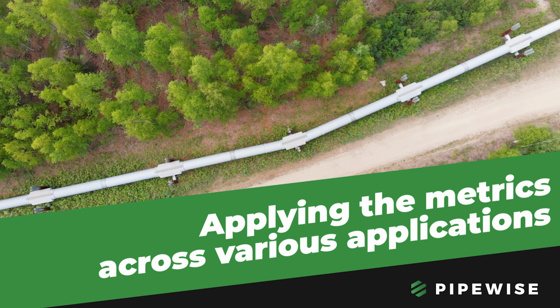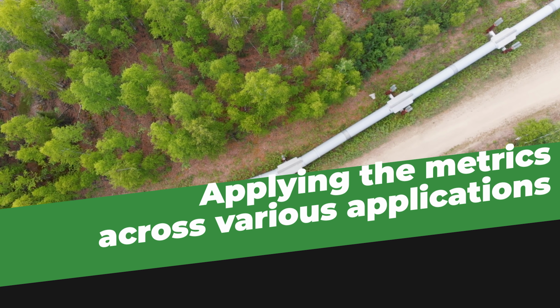Similarly, if we're predicting where along the pipeline that the leak is occurring, that's going to be tied into the sensitivity as well. So are we saying that it's occurring in kilometer 5 of a 100-kilometer pipeline? That really narrows the search space of where you're going to be trying to mobilize your assets to deal with that. And all 4 of these metrics work in tandem to make sure that you have a leak detection system that you can trust.